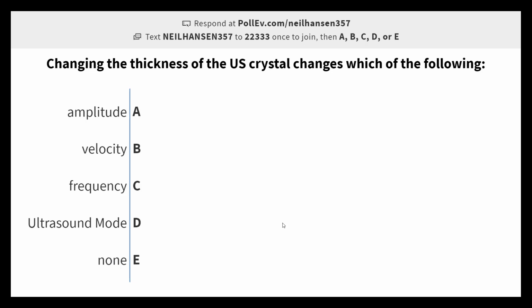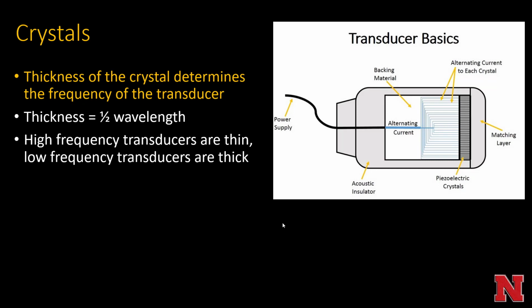Changing the thickness of an ultrasound crystal changes the frequency. The thickness of the crystal determines the frequency of the transducer, calculated as the thickness being about half the wavelength. High frequency transducers are thin, and low frequency transducers are thick.